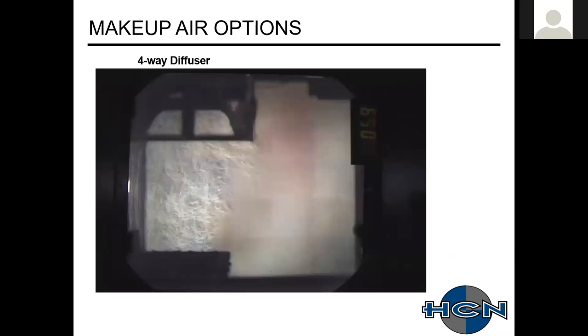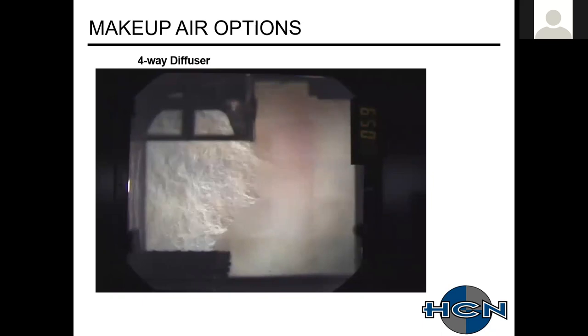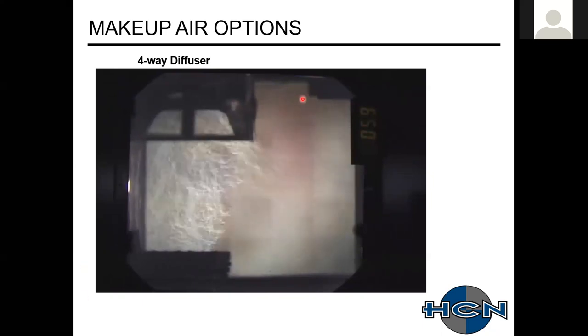The next one up was your four-way diffuser, located pretty close to the exhaust hoods. These are typically not the greatest to use. The reason for that is the high discharge, high throw interrupts and interferes with the hood capture. You can see from the video here, you're getting high discharge coming in here and it's pulling out some of the effluent because it's affecting the capture of the hood.